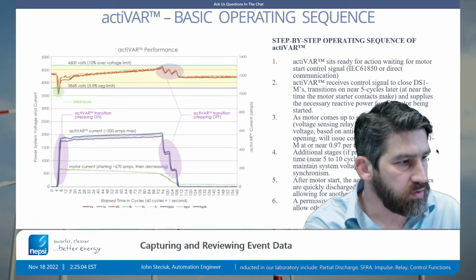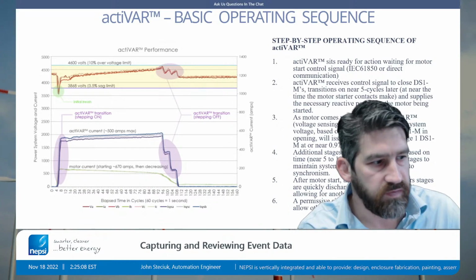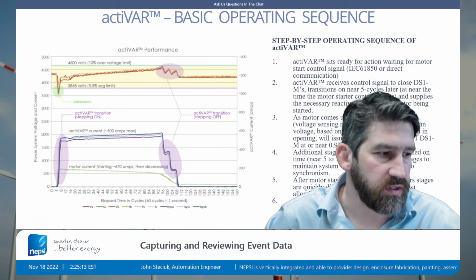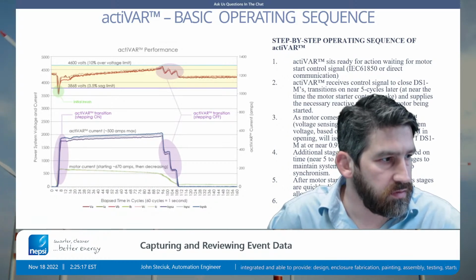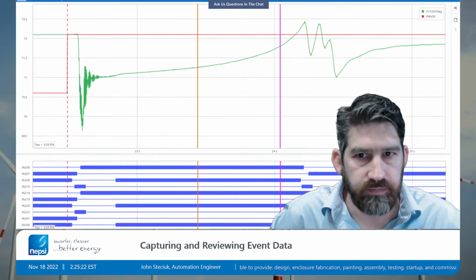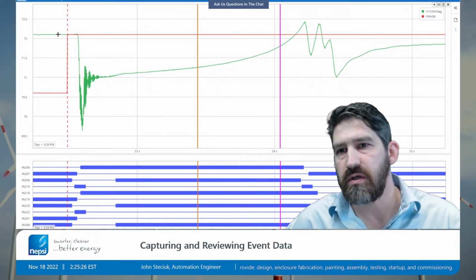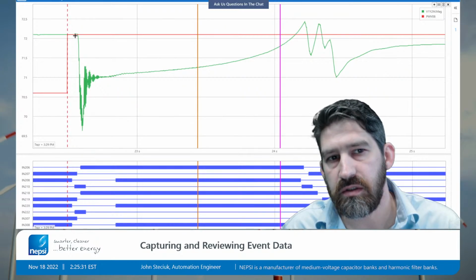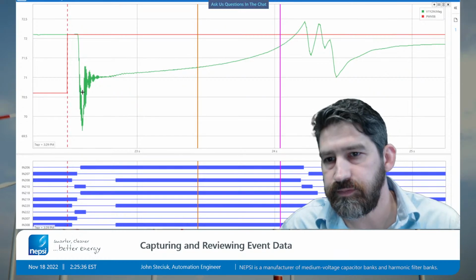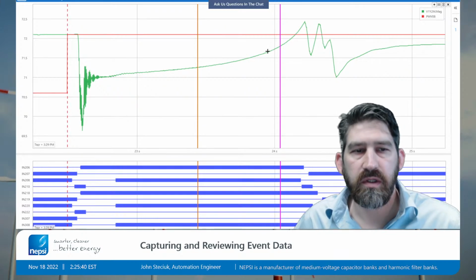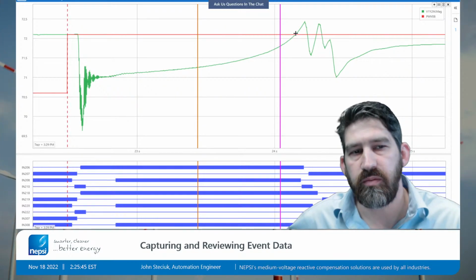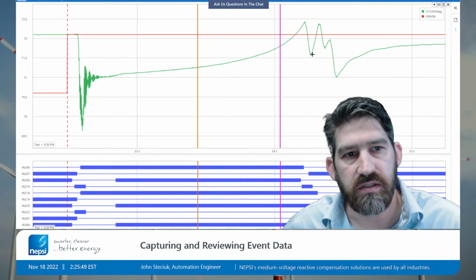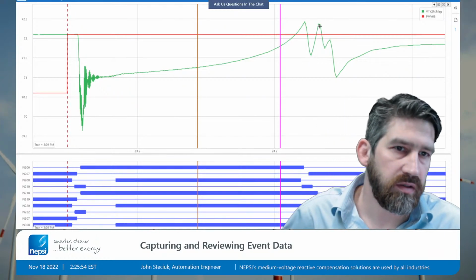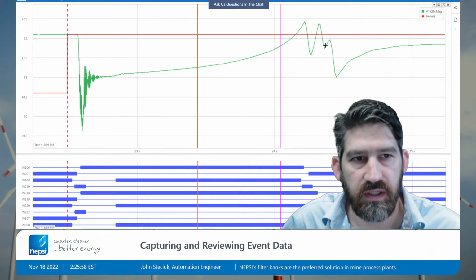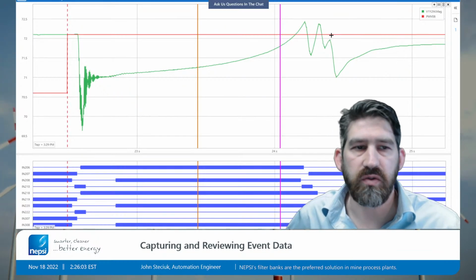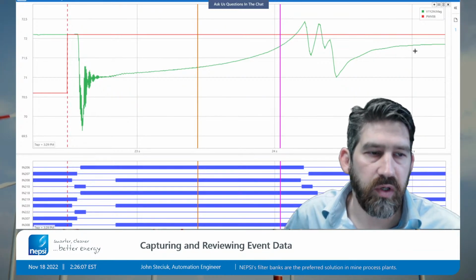And like I said, we have event reports that we used to help fine-tune both the front end and the back end with the timing. So we take a snapshot of the pre-start voltage, and when the motor starts, our capacitor stages turn on. So the voltage recovers quite a bit right away, and as the motor ramps up and slightly exceeds the pre-start voltage, that's when we kick our capacitor stages off. The motor continues to ramp up again. We slightly pass the pre-start voltage and kick the next stage off. The third stage is kicked off based on a short timer. And then the motor continues to ramp up and the voltage recovers.